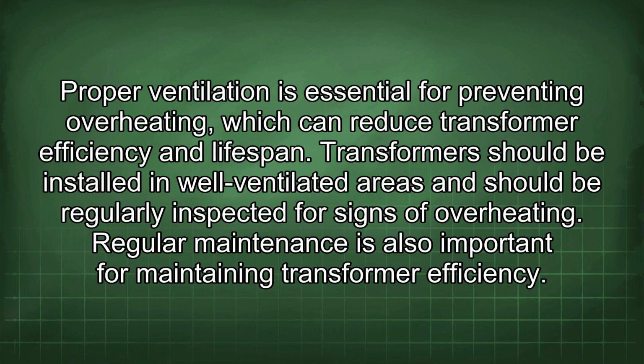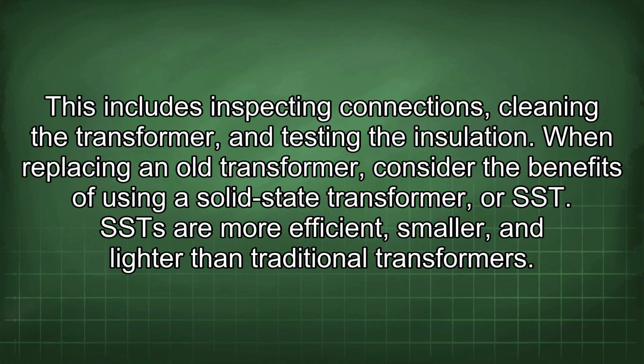Proper ventilation is essential for preventing overheating, which can reduce transformer efficiency and lifespan. Transformers should be installed in well-ventilated areas and should be regularly inspected for signs of overheating. Regular maintenance is also important for maintaining transformer efficiency. This includes inspecting connections, cleaning the transformer, and testing the insulation.